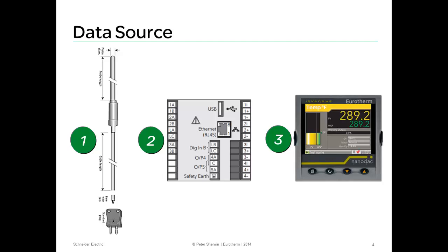What is the thermocouple type? The position within the furnace? Is this detecting the right temperature? When was it last changed? What is the calibration accuracy? A correction factor is added. Do you have a proper connection to the instrument? The correct lead wire and connector type limiting potential errors? What is the accuracy of the cold junction compensation and the instrument input accuracy? When was the instrument last calibrated? And what was the accuracy recorded? Any offsets used within the instrument? Assuming the above is all okay, we still need to know whether the conversion of millivolt to temperature scale is precise.